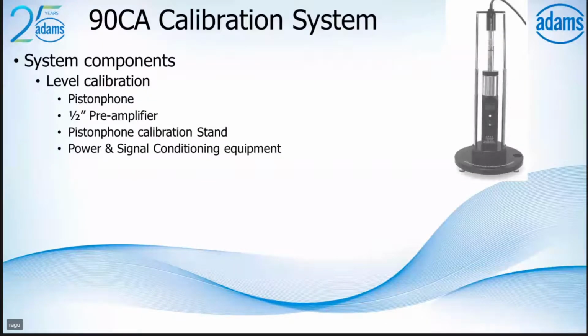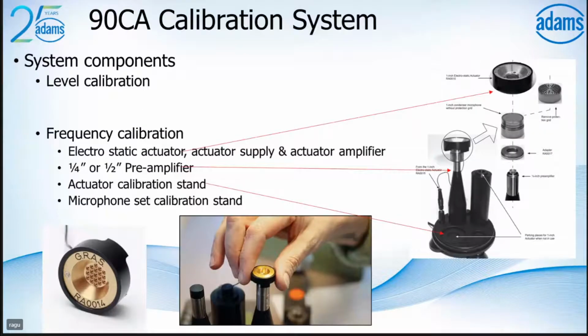These are the components in the calibration system. For level calibration, you have a piston phone, a preamplifier and a piston phone stand. You introduce the microphone capsule and do a level check at 250 Hz, 114 dB. Next is frequency calibration from 250 Hz to 20 kilohertz. You have the electrostatic actuator and the frequency response calibration stand. You mount the microphone and do a frequency response calibration.